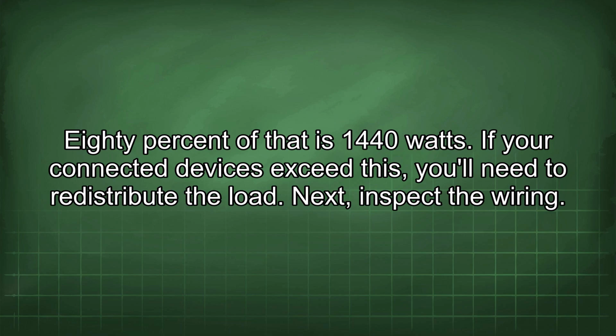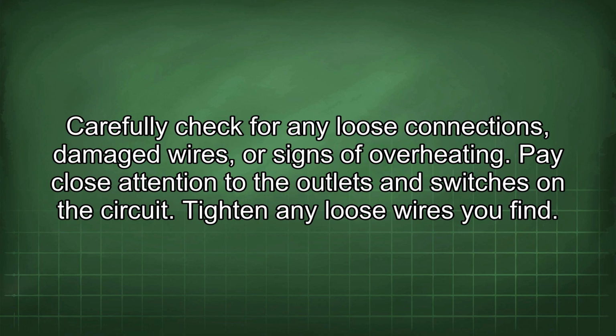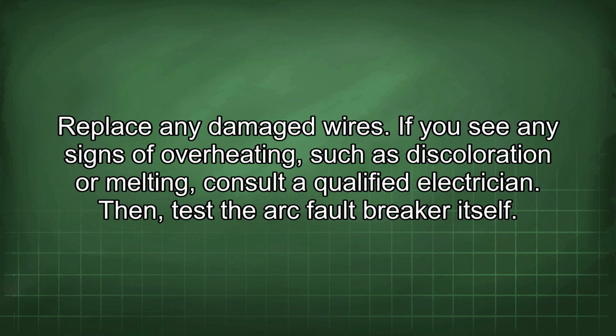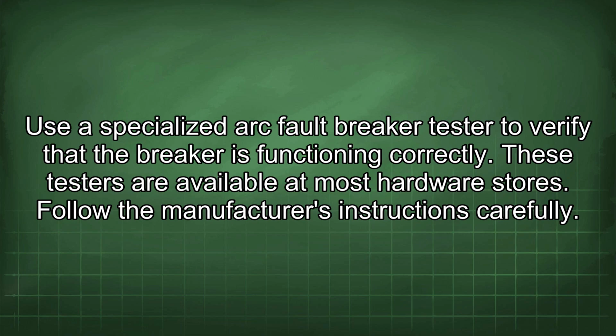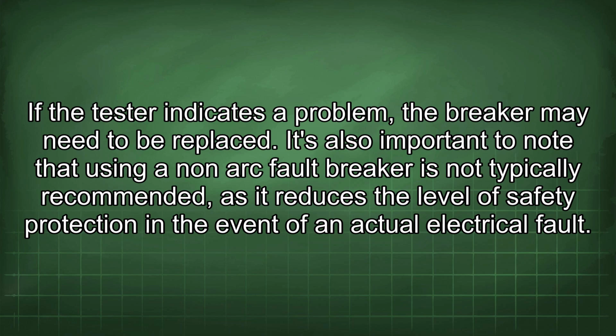Next, inspect the wiring. Carefully check for any loose connections, damaged wires, or signs of overheating. Pay close attention to the outlets and switches in the circuit. Tighten any loose wires you find. Replace any damaged wires. If you see any signs of overheating, such as discoloration or melting, consult a qualified electrician. Then test the arc fault breaker itself. Use a specialized arc fault breaker tester to verify that the breaker is functioning correctly. These testers are available at most hardware stores. Follow the manufacturer's instructions carefully. If the tester indicates a problem, the breaker may need to be replaced.